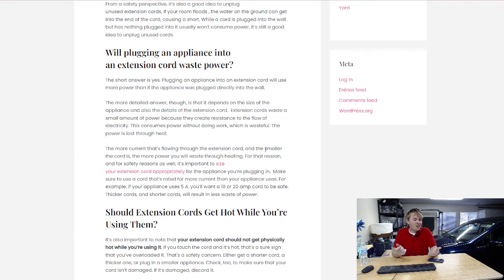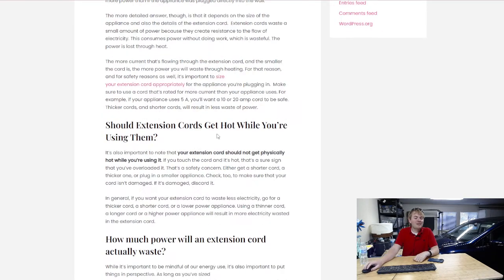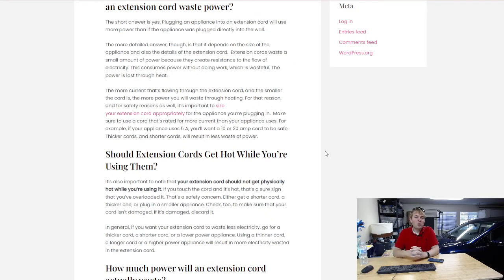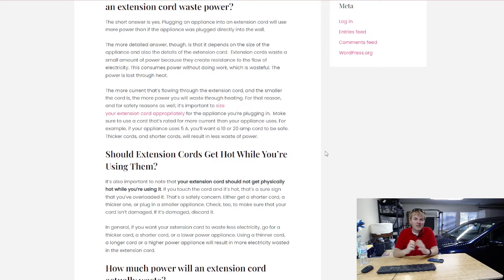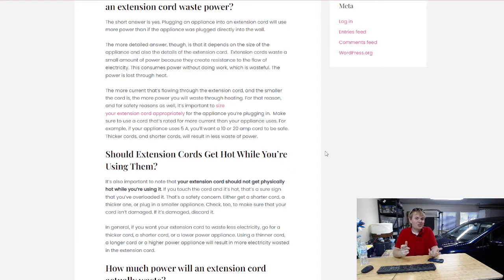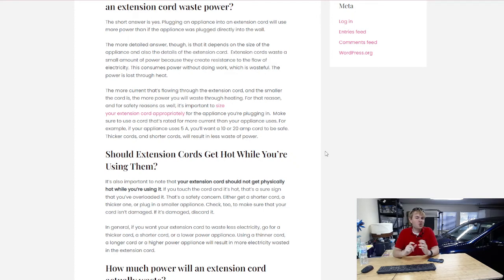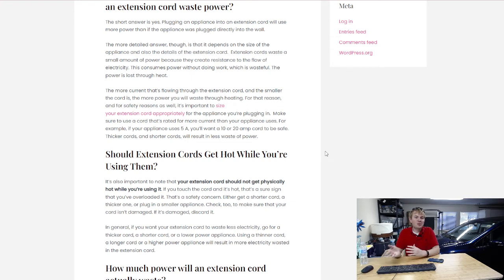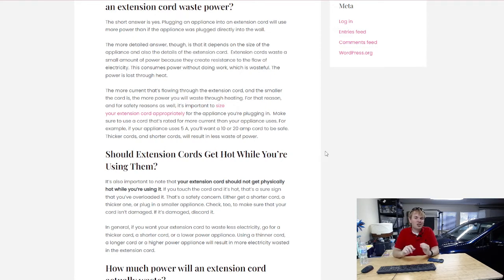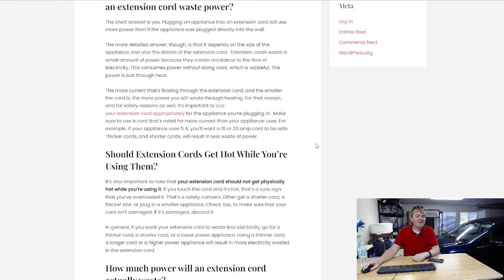One thing that you should note is that your extension cord should never get hot when you're touching it. If you feel it and it feels hot, then that means that your cord is too long or it's not a thick enough gauge, it's too thin for the load that you're putting on it, or the load is too high or you're plugging too many things into it or too big of a thing into it. It could also be damaged. If you're physically feeling heat on your cord, that's not a good thing. You want to replace that cord. Go for something shorter, go for something thicker, make sure that there's no damage on it, or reduce the load you're plugging into it. When I say you're wasting some power as heat in the cord, it's going to be a fairly minimal amount, not the amount that you could feel touching the cord. And that's very important from a safety perspective.